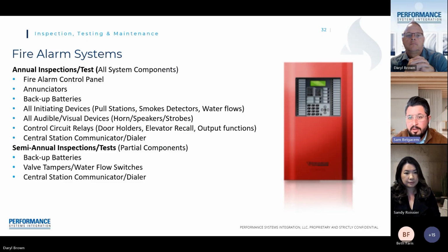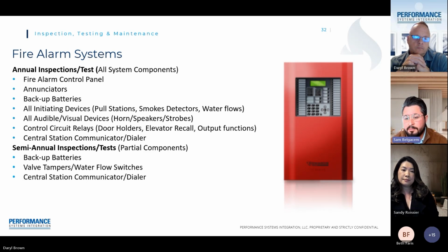To keep the system functioning the way it should, the NFPA 72 requires 2 types of inspections. The semi-annual inspection, which requires a visual inspection. So basically, we go to the site, we look at the system, we check the devices. There is nothing broken. There is no debris. We check the backup battery. We make sure that it's in good health and it will function when we need it. And we do an overall visual inspection.